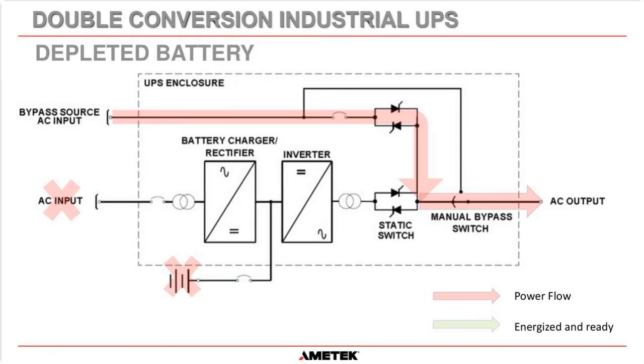Once again, we have to protect the batteries from going below a certain voltage that could irreparably damage them. For a 60 cell system, that's usually 105 volts DC, which is, if you do the calculation, 1.75 volts per cell times 60. So if the battery gets to 105 volts DC, our system immediately turns the bypass static switch on, then turns the inverter static switch off, and then trips this battery breaker to prevent the batteries discharging any more.